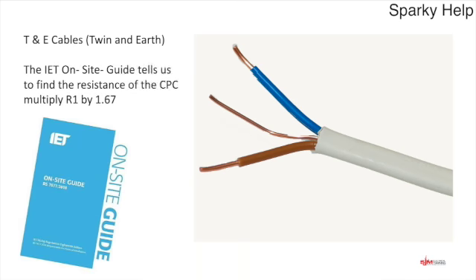But we don't. In the on-site guide it tells us that if you multiply your line conductor resistance by 1.67, because that's the ratio difference in conductor size, that would give you the resistance of R2, the CPC resistance, which would then allow you to go off and work out the adiabatic. However, we don't need to do that either, because there's a guide within the on-site guide, and it's one of these pages here.